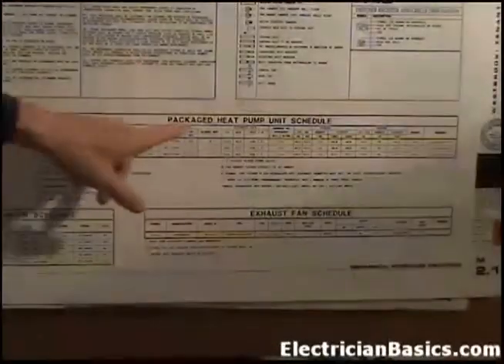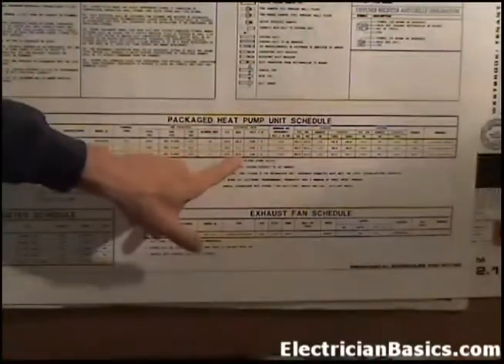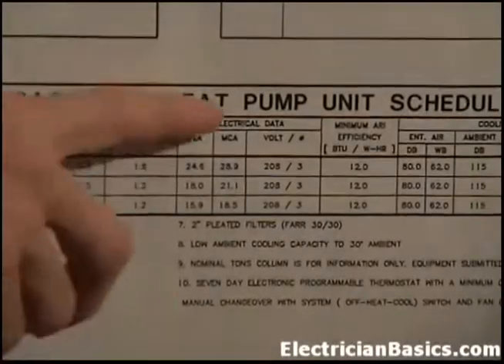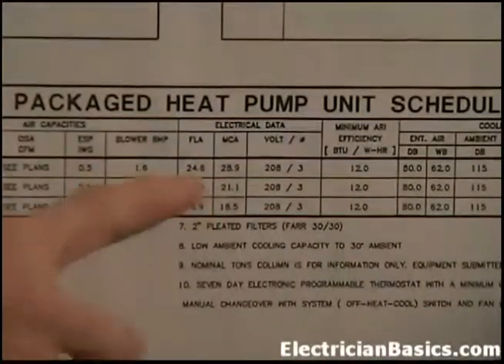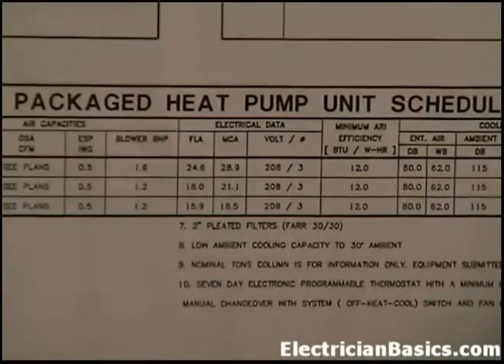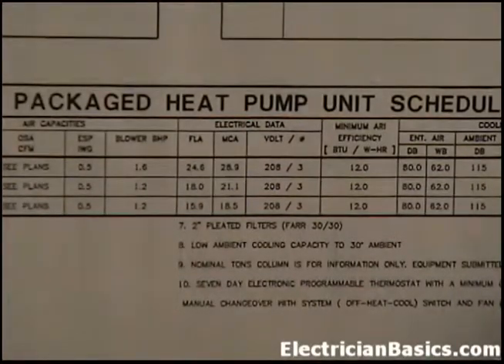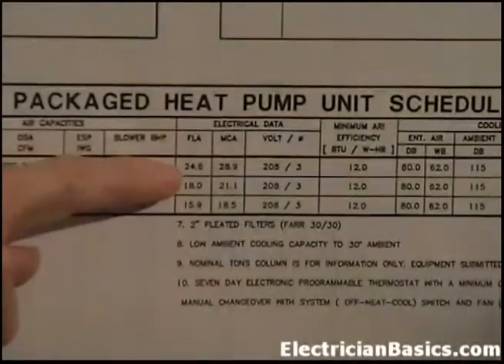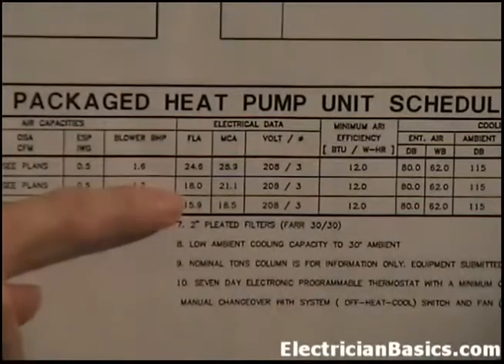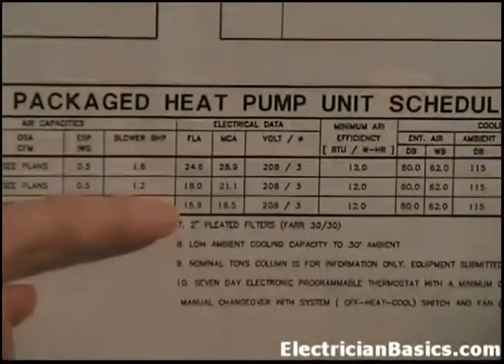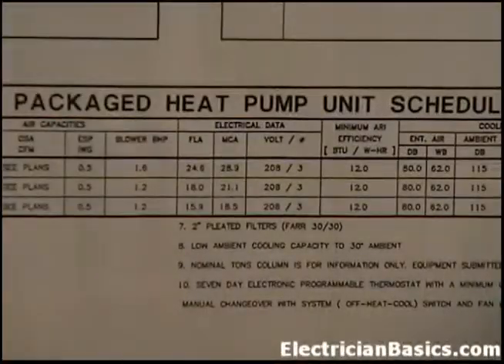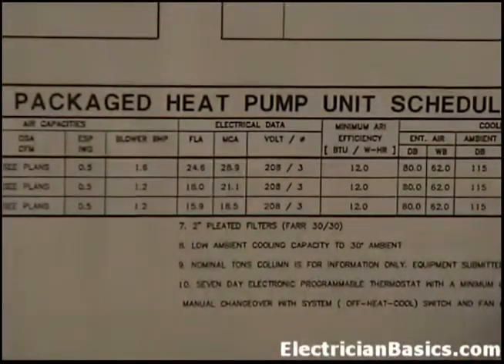Now, this information going across deals with the mechanical, but if we get in about the middle, under these large words, heat pump, you'll see electrical data. And what I want to do now is focus in on that. So here we are at electrical data, and we notice FLA. What that stands for is full load ampacity. In other words, when that is running at full speed, the full load ampacity is 24.6 amps. And that was the 5-ton unit, the 4-ton unit at 18 amps, and the 3-ton unit at 15.9 amps. And of course that makes sense because the bigger one draws more current.